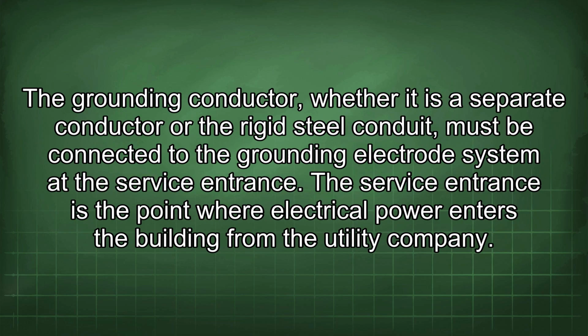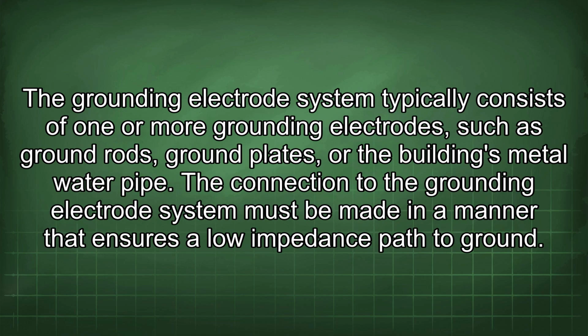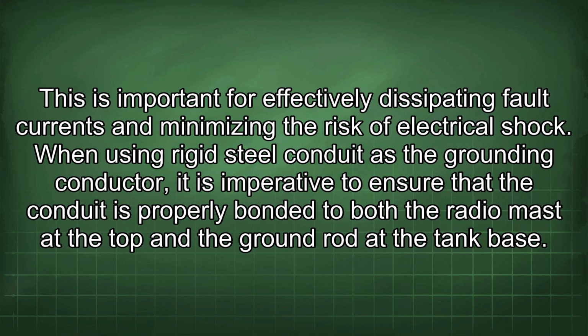The grounding conductor, whether it is a separate conductor or the rigid steel conduit, must be connected to the grounding electrode system at the service entrance. The service entrance is the point where electrical power enters the building from the utility company. The grounding electrode system typically consists of one or more grounding electrodes, such as ground rods, ground plates, or the building's metal water pipe. The connection to the grounding electrode system must be made in a manner that ensures a low impedance path to ground. This is important for effectively dissipating fault currents and minimizing the risk of electrical shock.